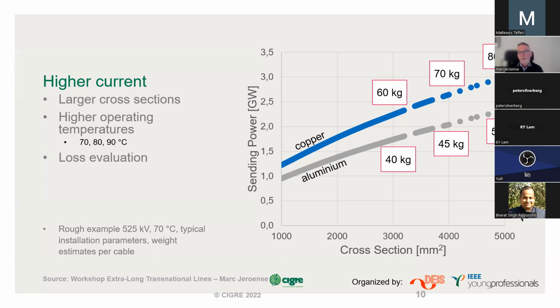It's quite some stuff. And therefore, it's important to realize that aluminum, although a less good conducting material, therefore less power for a cross section, has an advantage of lower weight, and definitely also of lower price, although the price levels are fluctuating like never before at the moment. But typically, aluminum has been at least 3 times cheaper the last 10, 20 years than copper. If you go further back in history, it was almost equal. But if it is significantly cheaper, then aluminum is a good example to use.